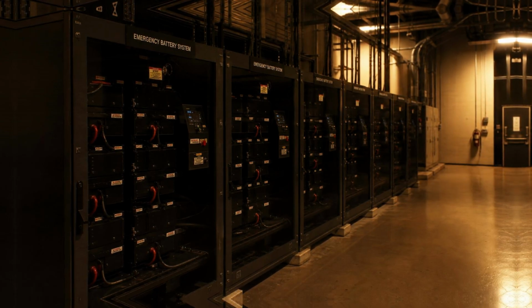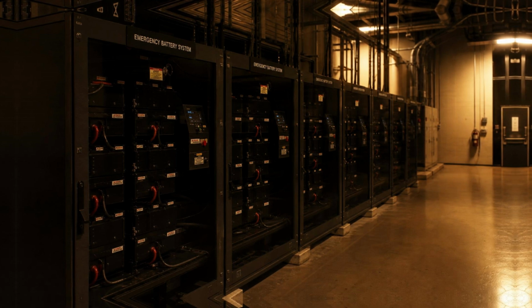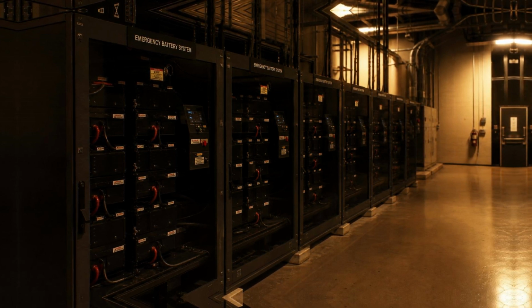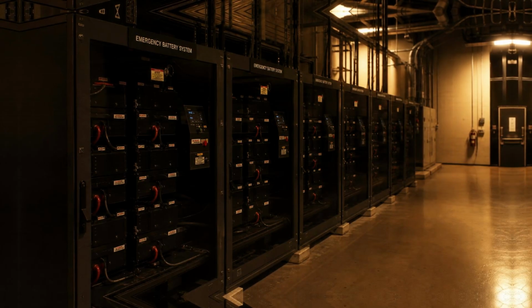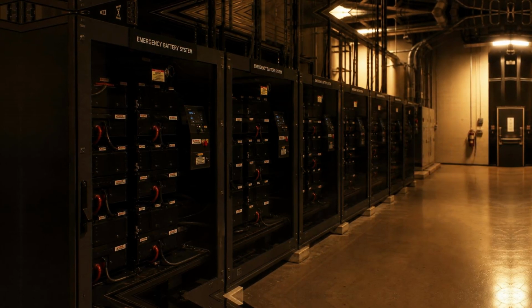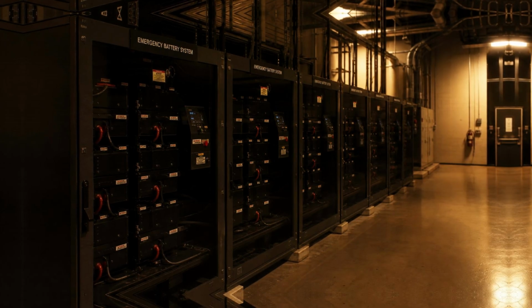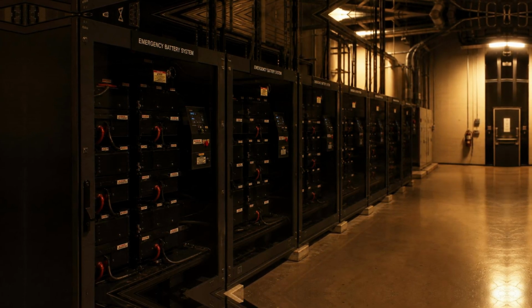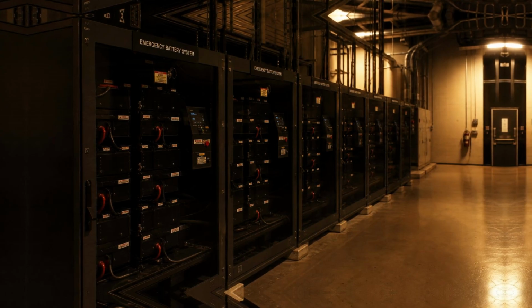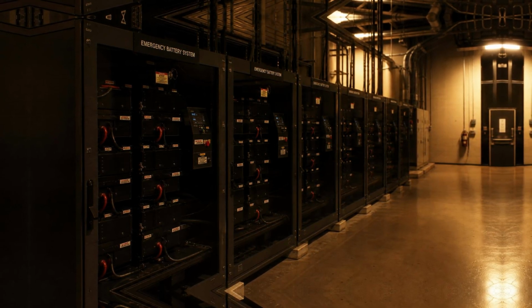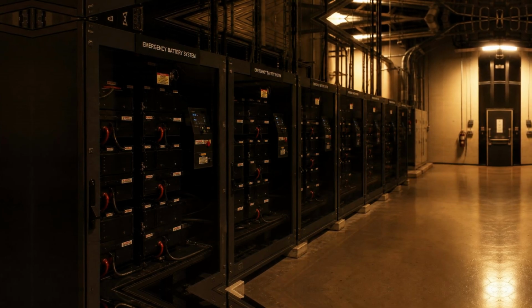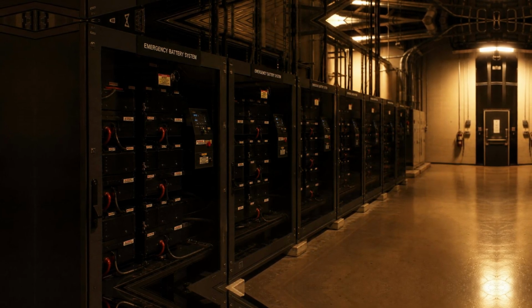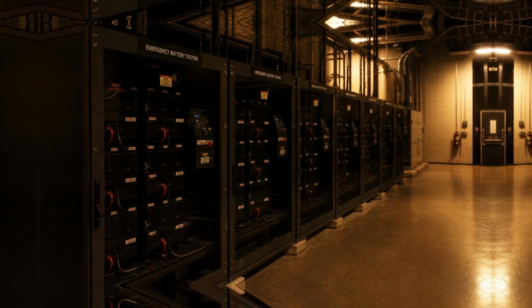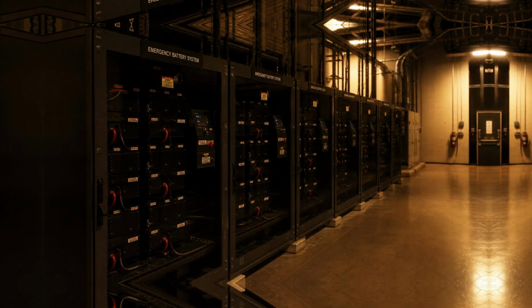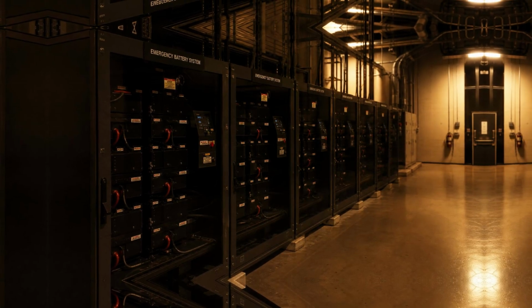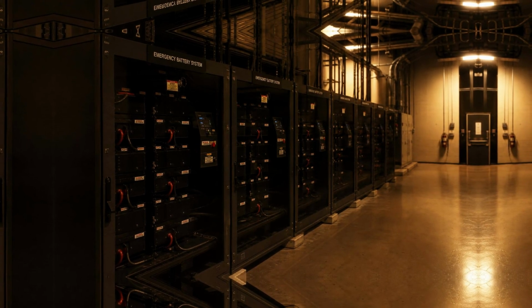Battery systems in commercial emergency power applications require a particular kind of ongoing attention, and it is worth sitting with what that attention looks like in practice. A battery does not announce its own decline. This is one of the fundamental truths of battery-dependent systems, and it is the reason that maintenance practices around batteries are so deliberate and so specific. A battery that is aging, losing capacity, increasing in internal resistance, approaching the point where it can no longer deliver its rated energy, may look entirely normal from the outside.